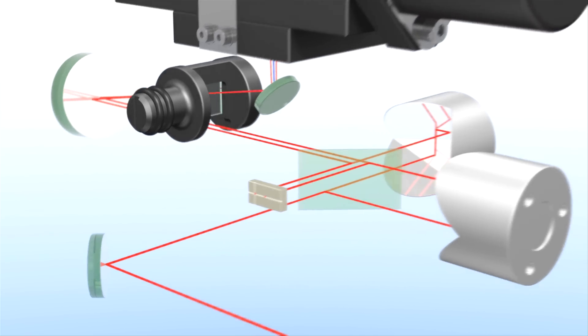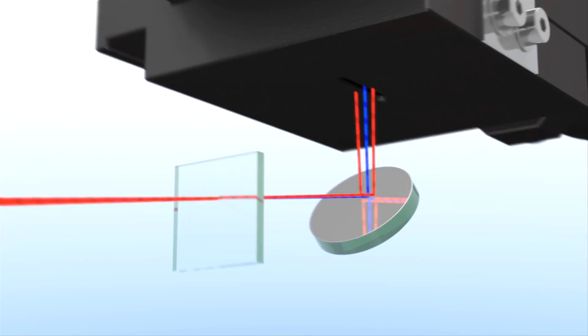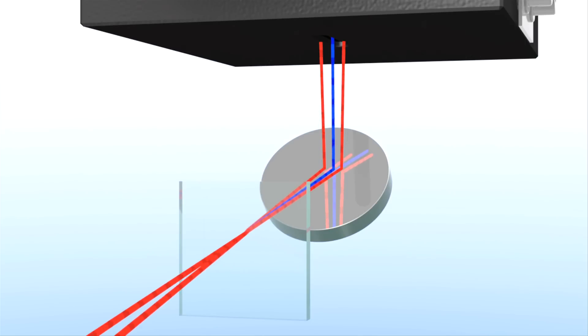By switching to non-collinear mode, both output beams no longer overlap at the detector and crosshair. Now they only overlap in the crystal. The result is a background-free SHG intensity autocorrelation signal.